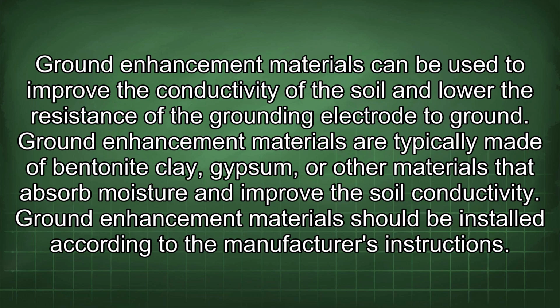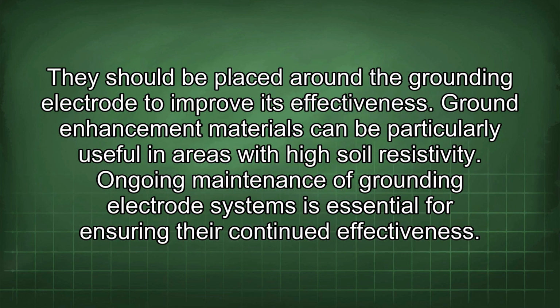Ground enhancement materials can be used to improve the conductivity of the soil and lower the resistance of the grounding electrode to ground. Ground enhancement materials are typically made of bentonite clay, gypsum, or other materials that absorb moisture and improve the soil conductivity. Ground enhancement material should be installed according to the manufacturer's instructions. They should be placed around the grounding electrode to improve its effectiveness. Ground enhancement materials can be particularly useful in areas with high soil resistivity.